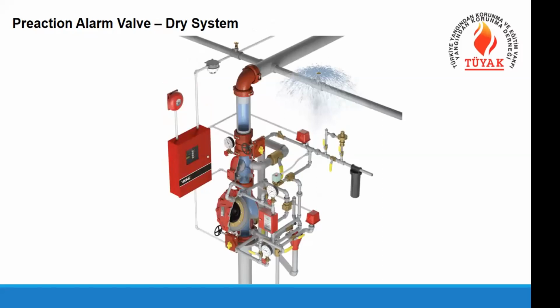And we have another system called a pre-action system. Pre-action valve systems, as coming from the name, are pre-action and pre-alarm systems. So when you have, for example, here we see a double interlock pre-action system, and when you have this kind of system, the only way you will see water coming from the sprinklers is activation of the sprinkler and the detection both activated at the same time.